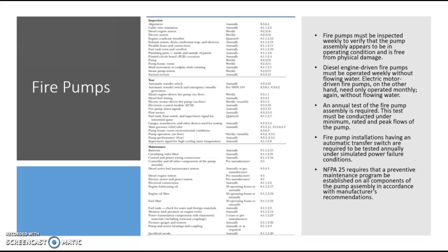They have to make sure that an annual test of it is required. It must be conducted under the minimum rated and peak flows of the pump. Fire pump installations having an automatic transfer switch are also required to be tested under the simulated power failure condition. So you drop power, make sure that the paralleling gear brings up the ATS of the fire pump. The ATS can properly run and energize the equipment, and then the equipment can come up.